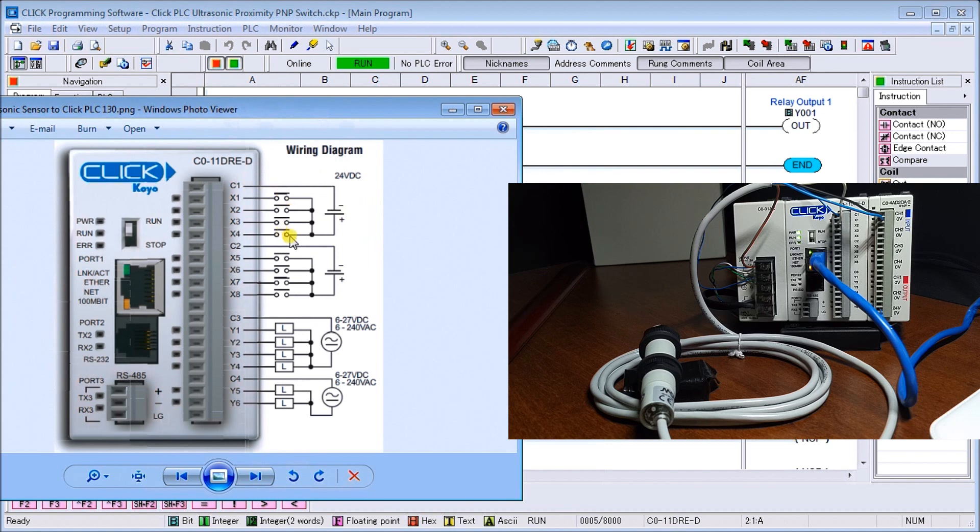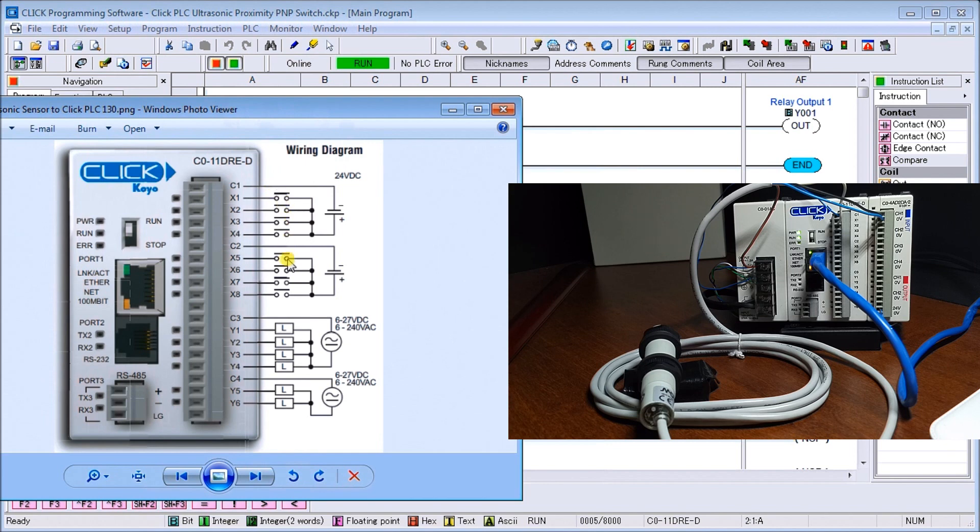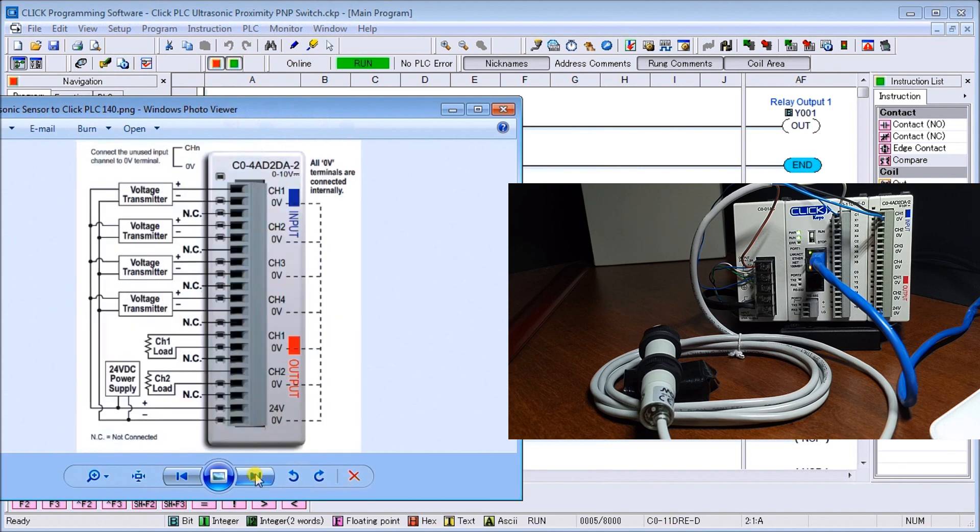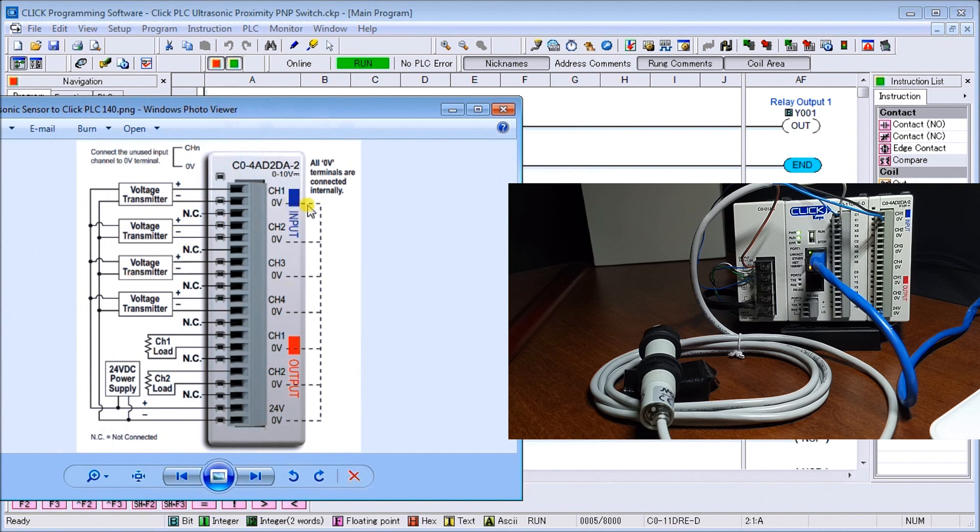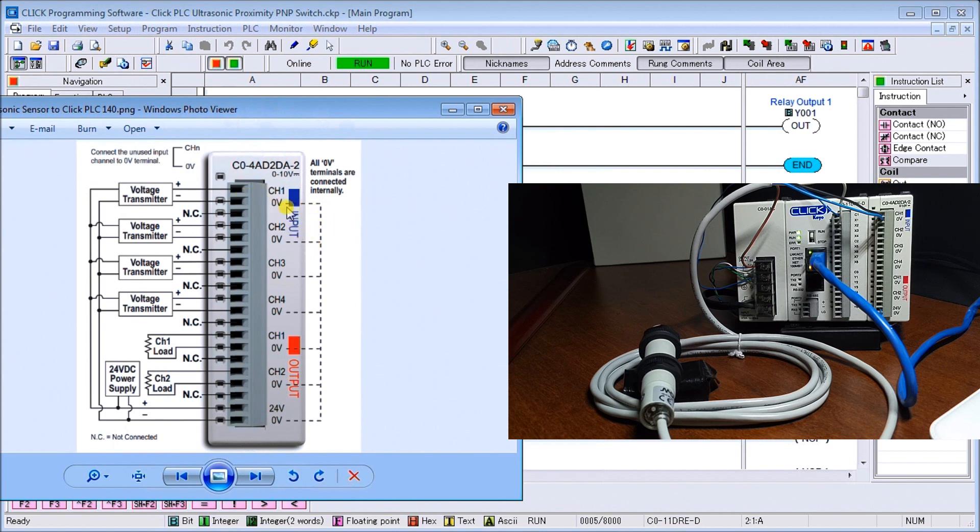You can see here, here's my wiring diagram for my Click. C1 can be wired either way, NPN or PNP. NPN meaning negative switching or sinking a load. Then we have our analog, and one important point is that all the zero volt terminals are connected internally, so when I put a zero volt on there it's the same as one here, which is why we connected the blue wire right here into our zero volts.